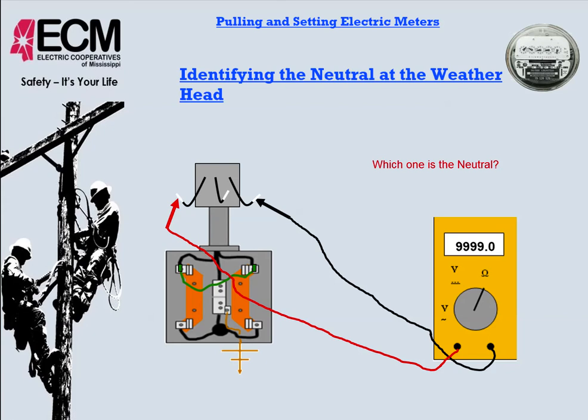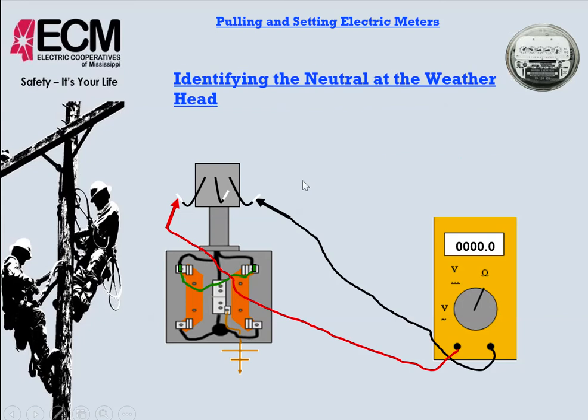Well, actually, we don't know, because we're looking for continuity between these 2 wires, right? So we want to identify our 2 hot legs, and then our odd one is going to be our neutral, okay? So if we put our wire across these 2, and then we touch the 2 leads, and it shows 0 ohms of resistance, that means that these 2 are the hot legs. So then we would ask the question, which one is our neutral? Well, obviously, it would be the one not being tested. If we touch 2 together and it shows 0 ohms of resistance, that's showing continuity, okay?